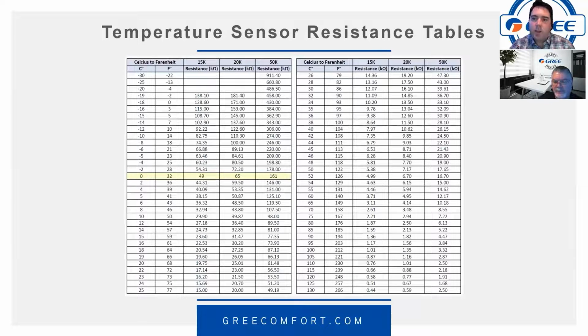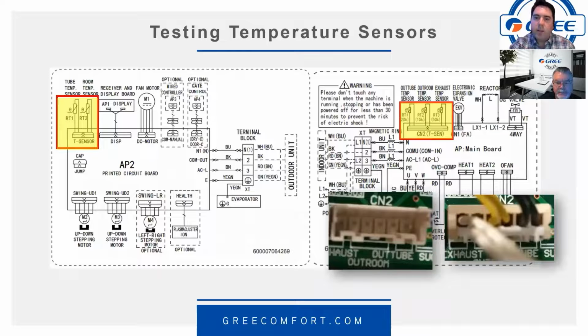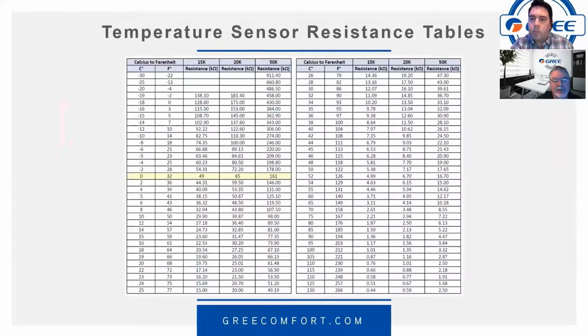And generally speaking, as you can see in the previous picture, Keith, the color of the wires going to the sensors. Now this is generally speaking. There may be a few different ones in the older versions, but from all of the current models that I deal with, I see the white being the 50K, which is the discharge. I see the yellow always being the ambient sensor, and it's the entire wire, and the sensor itself seems to be yellow for indoor and outdoor ambient, so it's easy to recognize. And then the black wire is the 20K coil sensors, and on the multi-zone you'll see several of the black wired 20K sensors on the outdoor. Yeah, that is helpful. So just at a glance, you should be able to tell.